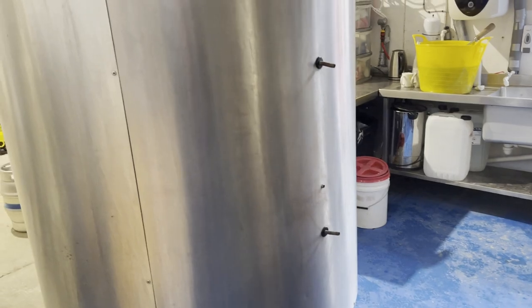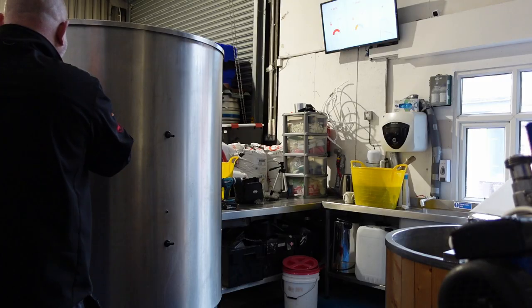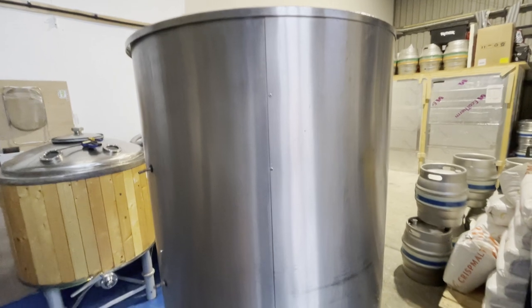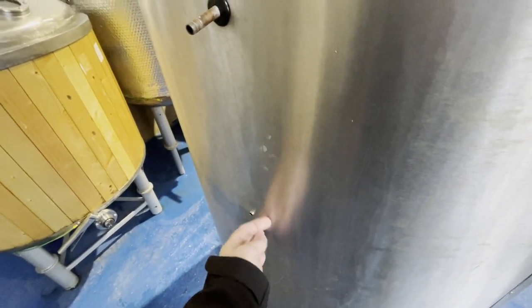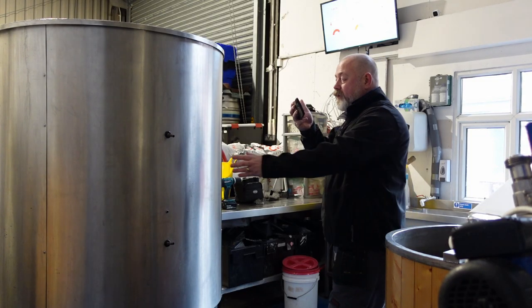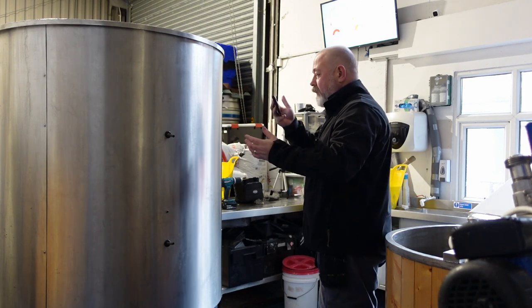So what we're going to do — somewhere in here, just to show you the rough construction. This tank is clad with about 0.8mm stainless, riveted all the way down on both sides. You've got the input and output pipes for the glycol and a little thermo well. I am hoping the freeze is somewhere in there. This was the point closest to the wall in the corner where it was coldest, so logically we'll start there.